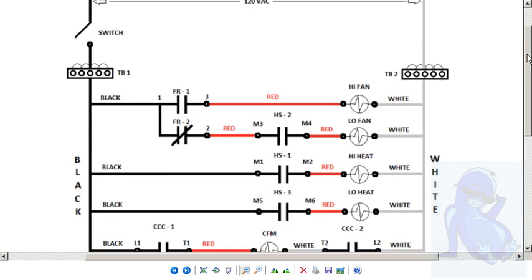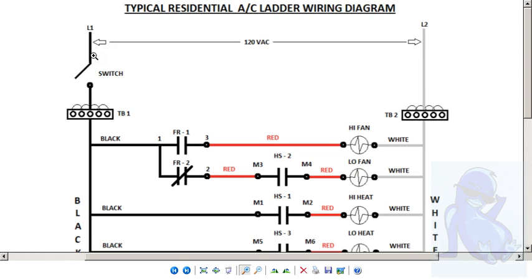In some ladder schematics, you will see before the switch a line drawn to a little heat coil that goes on the compressor, and then it ties in over here, because basically that's the one exception where you really don't need a switch. We want that compressor heater to come on as soon as it's plugged in, and that tiny little bit of heat is going to separate the refrigerant oil and the refrigerant, so the refrigerant will go away. Otherwise the refrigerant will settle and mix into the crankcase of the compressor, and we want a little bit of heat there to encourage the freon, the refrigerant, to migrate somewhere else, because the refrigerant always tends to migrate to the coldest spot.